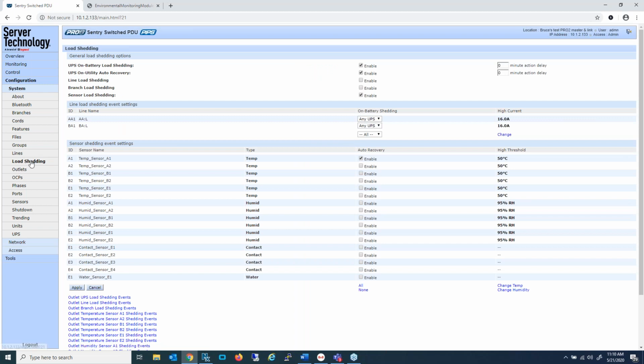Okay, so we've gone back to the primary load shedding page. You do need to enable the UPS on battery load shedding. By default, all of the load shedding is disabled. So simply updating firmware to get this feature, there is no risk that you could end up having things switch off as a result of a load shedding event. I have enabled load shedding for the UPS on battery.